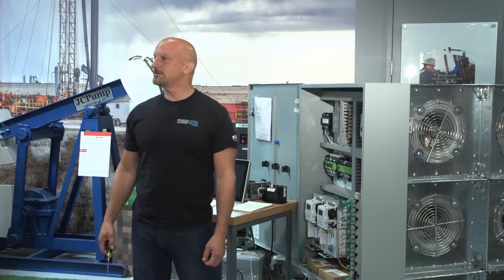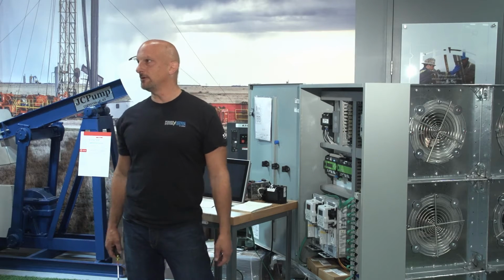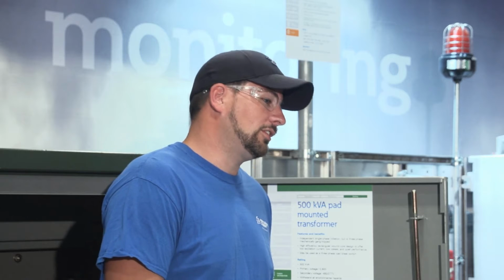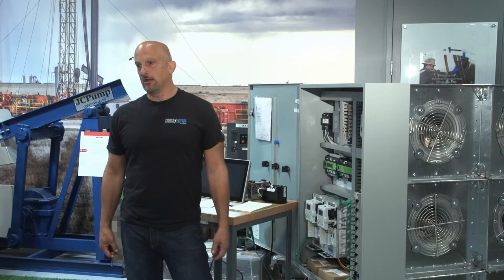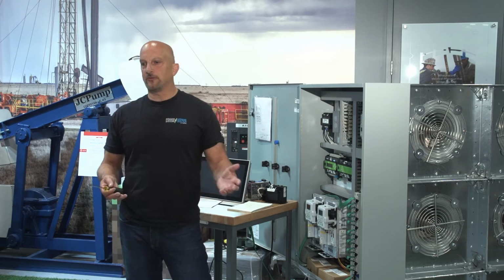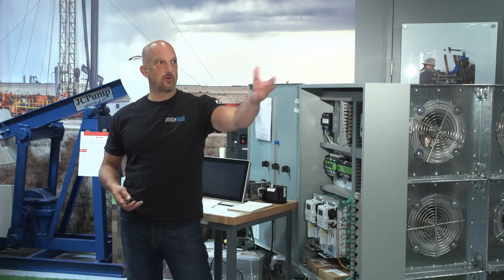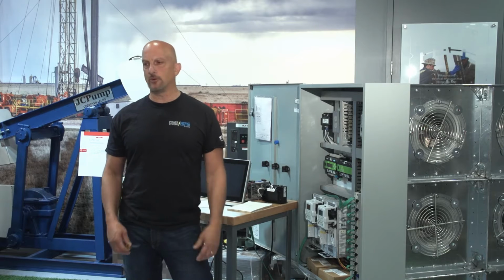Rick, how about for electricians? Is it really pretty straightforward, or do they kind of know what they're doing? We run into a lot of confusion about grounding and bonding as far as transformers, bonding XO, when to bond, where to bond, with the different starts and stops of service, earth ground, building steel, foundation grounds. There's a lot of confusion based on that. I see it with power quality: if it's 3-wire, 4-wire, transfer switches, all this kind of stuff, even coming down the pole, going into the resi room here, where do we ground it, where do we bond it?